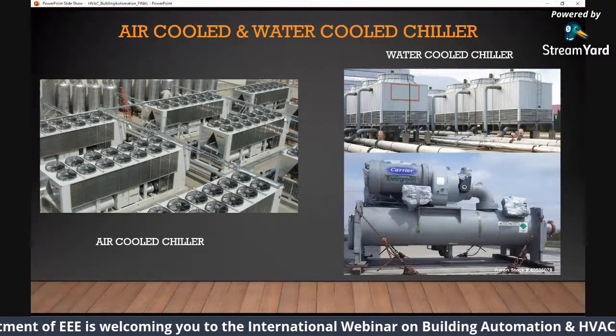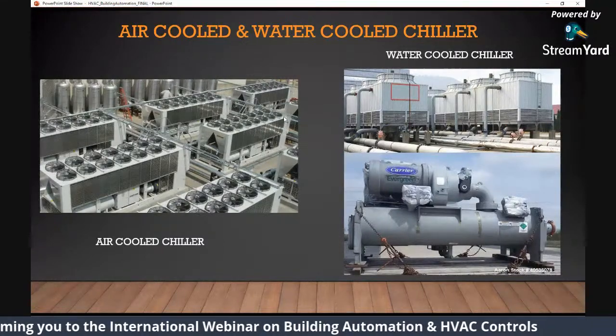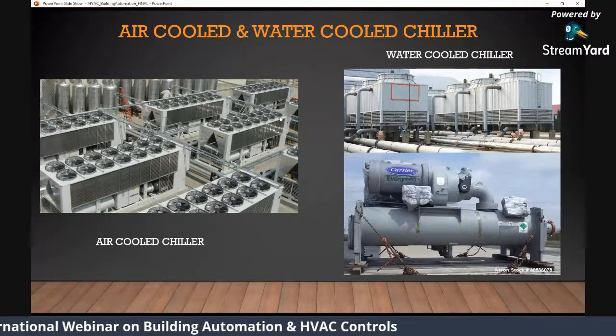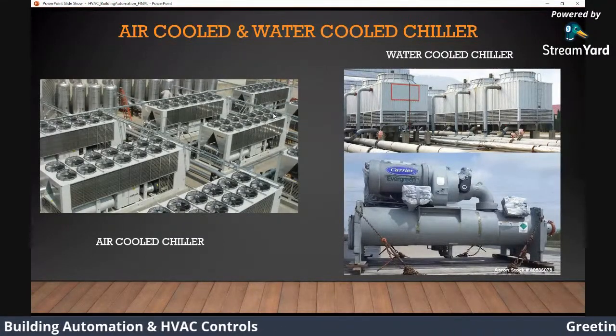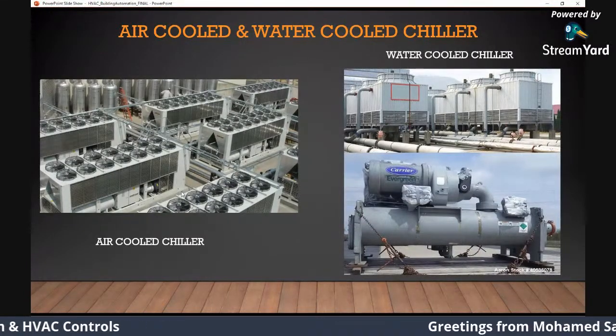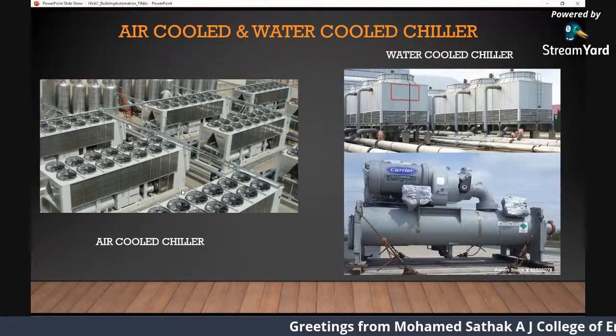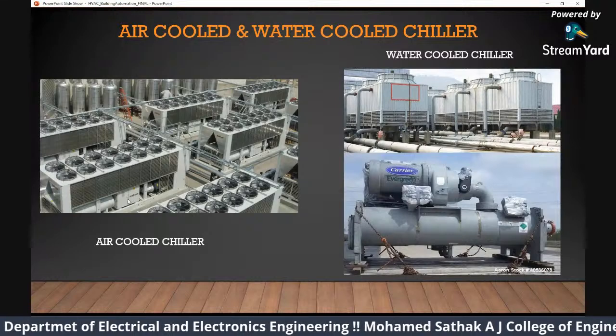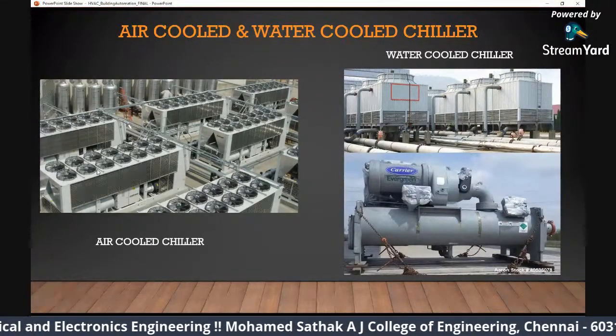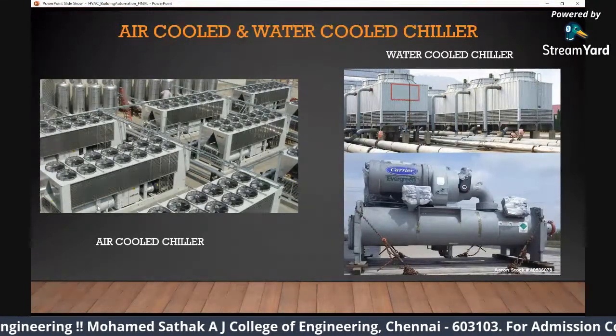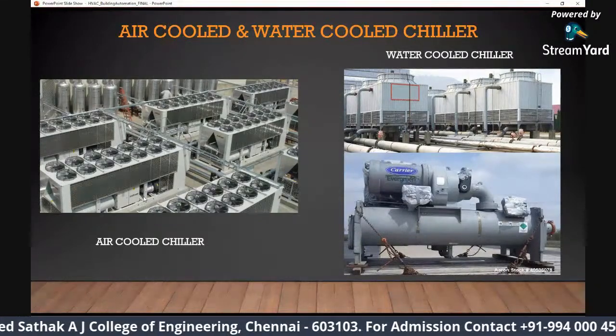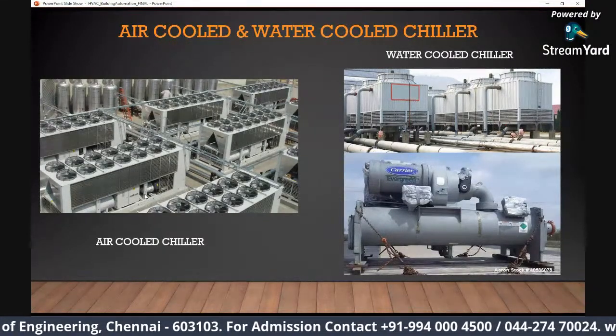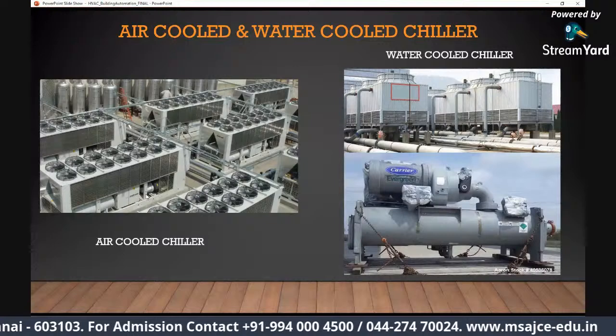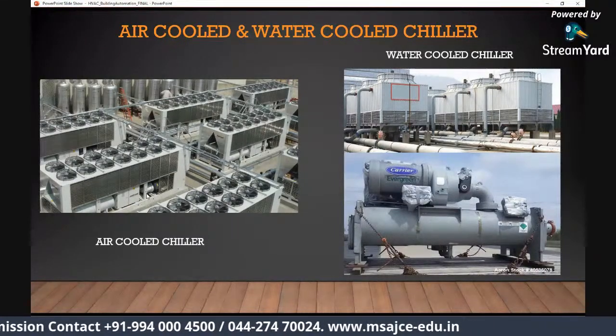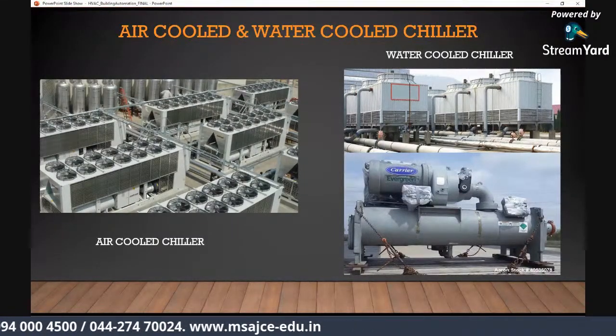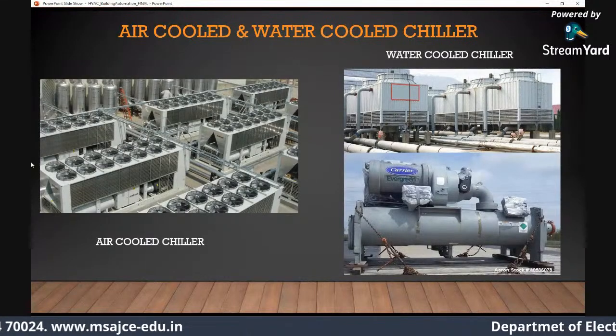So chillers can be classified into two types. We call them air cooled chiller and water cooled chiller. On what basis do we classify them? Let's say, for example, the split AC, we call it an air cooled chiller because if you see the picture on the left, there are multiple fans on top, and there is a bottom cubical or cylindrical structure. We call it the evaporator part. There is a refrigerant inside the evaporator part which cools the air or cools the water for the building, right? Now that refrigerant needs to be cooled, and that is taken care of by your fans.